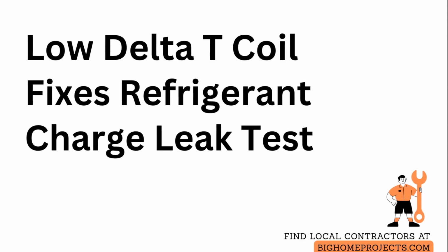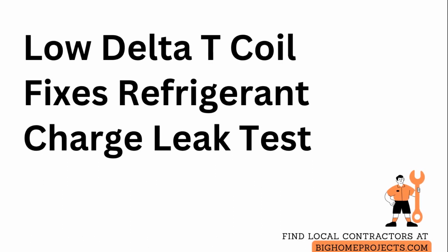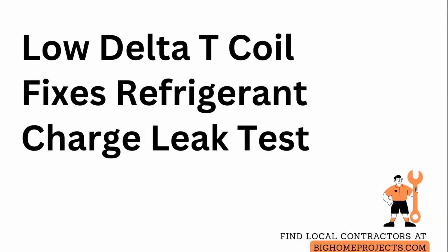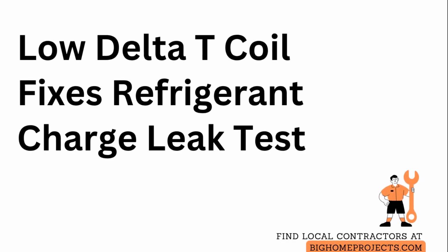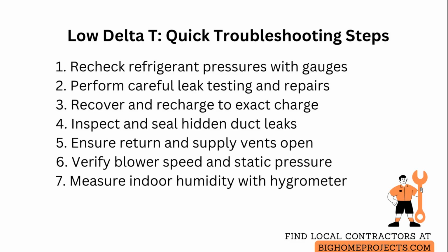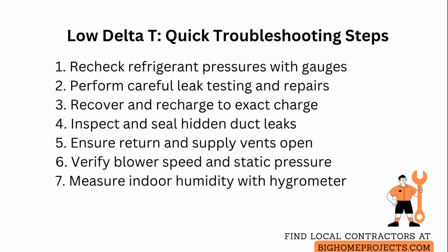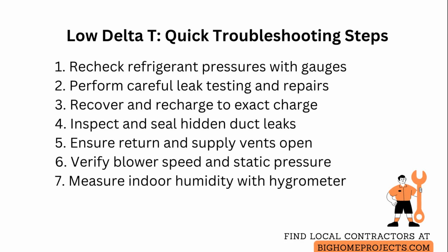If the temperature drop across the coil remains too low after cleaning and repairs, treat it as an unresolved performance issue that requires systematic troubleshooting. Start by rechecking refrigerant pressures with a gauge set and compare measured high and low side readings to the manufacturer's specification for the refrigerant charge and ambient conditions.